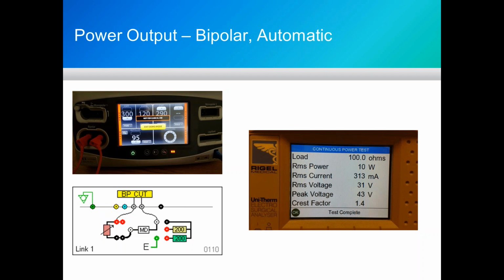So we're going to come from the active electrode through our resistor that we will adjust for 100 ohms, through our current transformer, and then back to the dissipative side on the generator itself. And then on the right-hand side is just a photo caption of the test data that was captured.